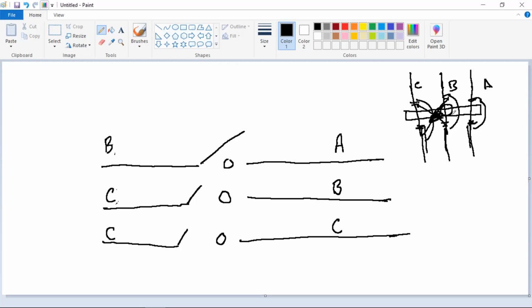But even with that, they still want the radio communication and a confirmed field switch order that phasing was done. All right, so you run into a situation. I'm going to put a phasing stick, and we'll say this is 7,200 volts on this side, 7,200 volts on this side. I put my phasing stick here, and my other phasing stick over here. What should the reading be on the Hastings meter? 12,470, right? Correct. Which is bad. Obviously, I know I cannot close that switch, and we have to back up and find a resolution before we can do any switch closures.